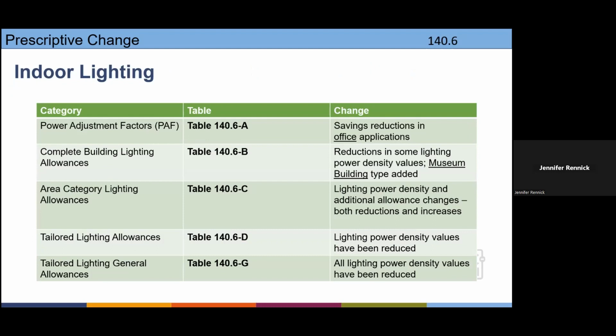Indoor lighting, there has really not been many changes on the indoor lighting. A few categories have become a little more energy efficient, and I haven't noticed that this is going to be a problem because so many projects use LED lighting anyway. But where you might notice this on the performance method is if, as an architect or mechanical engineer, you're always counting on having a big cushion on your electric lighting, part of the LPD, lighting power density budget, some of that's going to go away. So you can't depend on the lighting making up for the rest of the performance.